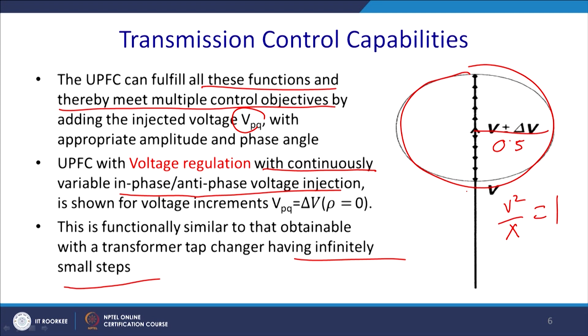UPFC with voltage regulation, with continuously variable in-phase and anti-phase voltage injection, is shown in this figure for VPQ equal to delta V, where it is in phase, thus rho equal to 0. This function is similar to the tap changing transformer having infinitely small step change. So, you can inject very precisely, and thus the harmonic content is greatly reduced. You do not have a problem of harmonics.